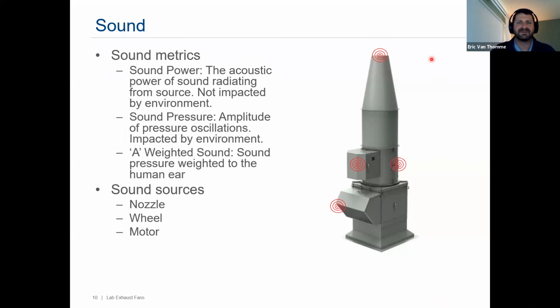You're going to have some sound metrics that incorporate this outlet area, as well as some of the motor noise and the fan noise. And then you're also going to have some sound coming through this bypass damper. So there's a number of criteria to consider from a sound perspective, and all of our submittal documentation can help you compare one fan selection versus another.